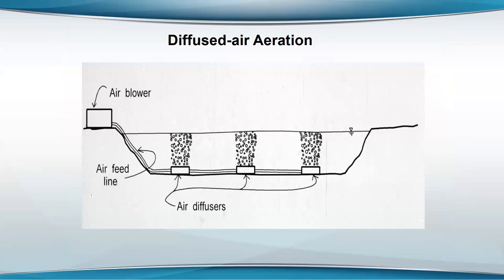Diffused air aeration systems use an air blower to release oxygen through an underwater diffuser. A big problem is that the water depth is usually not great enough for the bubble hang time to allow much oxygen transfer — they may only transfer one or two percent of the oxygen in the bubble. Those are not very efficient generally, but if you've got a deeper tank, they are. Diffusers are nice because you can use one device to power many individual units.